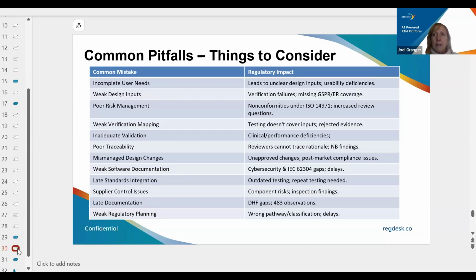Design changes over time: if you have made changes to your design and then not adequately assessed the regulatory impact, but also the impact on any testing that was done previously. Do you need to repeat certain testing? Then those certainly will get you into trouble when a regulator finds it. Software documentation: if your product does contain software, you'll need to worry about cybersecurity and IEC 62304 requirements. Not meeting all of them will cause delays in the review process, or rejection or non-approval of your device. Late standards integration: again, you need to identify the standards that you're going to need to meet at the front end, before you've done your testing. Otherwise, you're going to have to go back and repeat that testing, which can be very costly and time consuming.